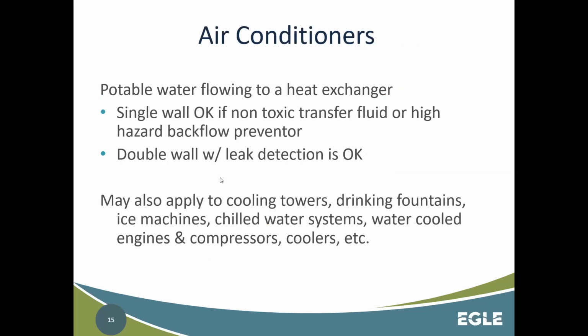The next potential risk is actually air conditioners, at least some air conditioners. Depending on the models, there are going to be some that have water flowing through them, kind of acting as a heat exchanger for how the unit functions. We have examples of heat exchangers on the next slide. With the design, the protection between your actual flow of water and, again, with this heat exchanger, it's okay if it's only a single wall protection, as long as there is non-toxic transfer fluid or you have a high hazard backflow preventer in place.